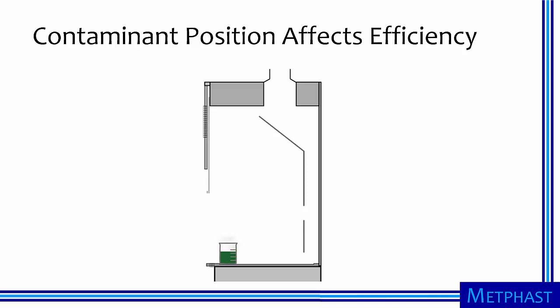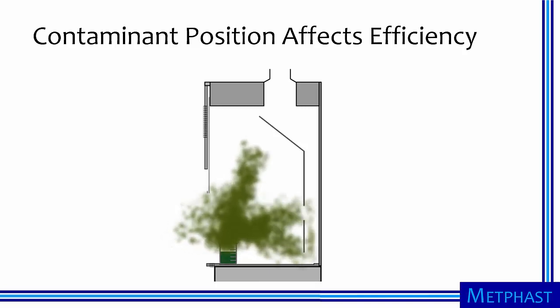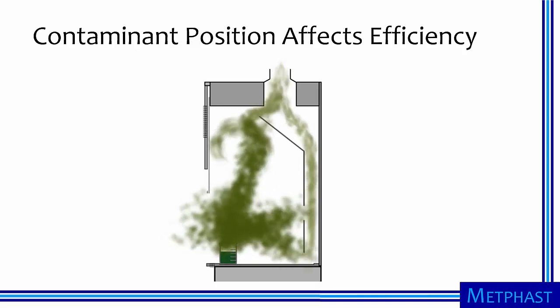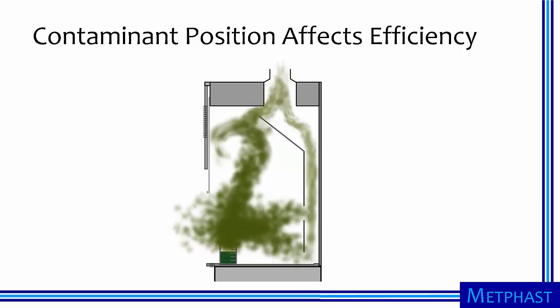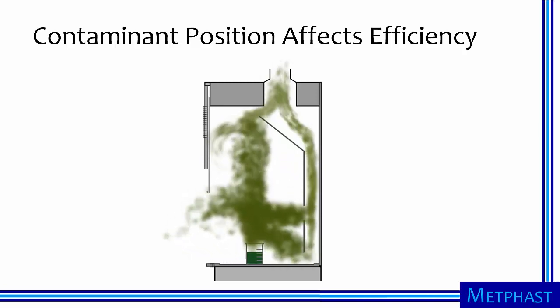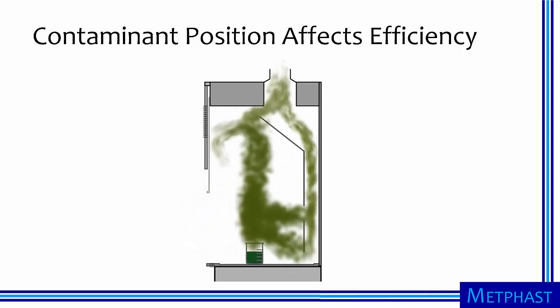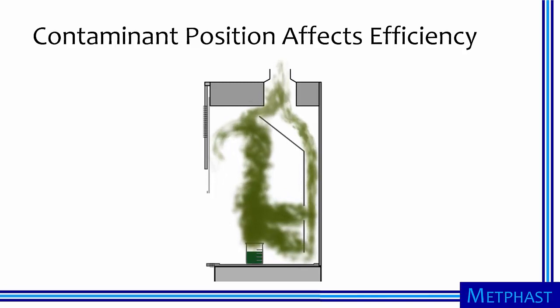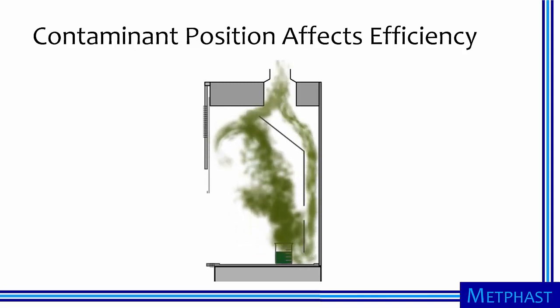The position of items emitting contaminants, or sources, affects the efficiency of the chemical fume hood. Sources placed near the front of the hood can escape capture. Instead, sources should be placed at least 6 inches and preferably 10 inches from the opening so that contaminants can follow a safe path toward the exhaust duct. Although harder to reach, contaminants from sources placed near the back of the hood will typically stay away from the front opening.